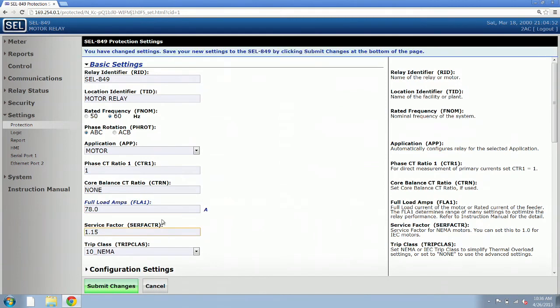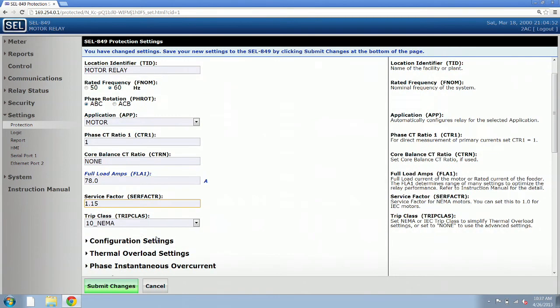Then we need to verify the service factor. Again, that's right off the nameplate of the motor. Our example motor has a service factor of 1.15, which matches the default, so we're done.